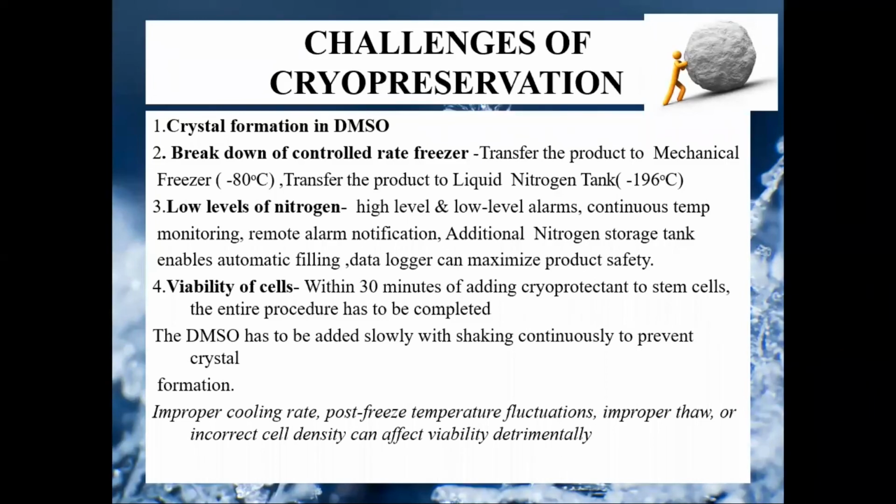For that, you can attach an additional nitrogen tank to the storage tank so that there will be continuous supply of nitrogen. And there should also be high level and low level alarms and remote alarm notification. You can also use a data logger for the automatic filling.